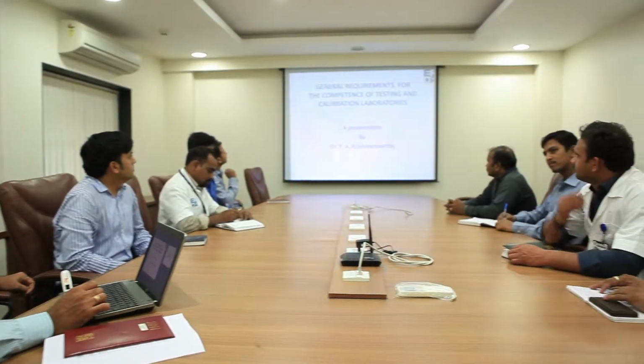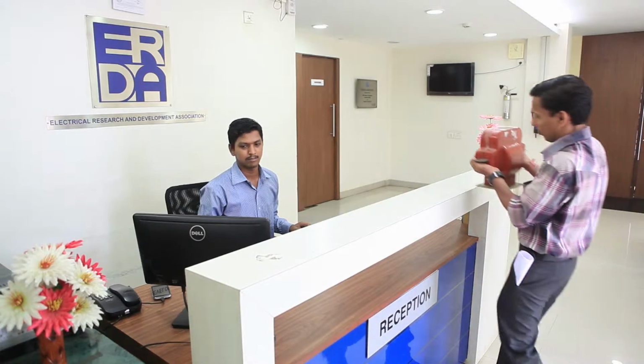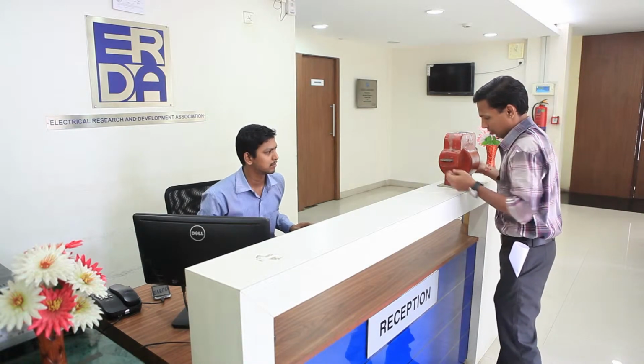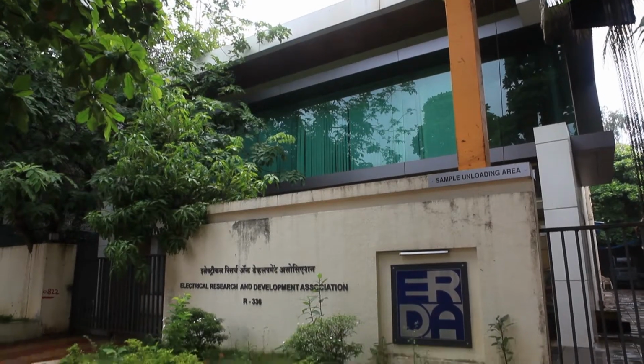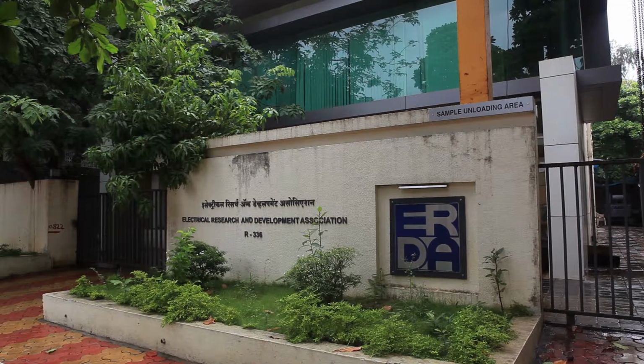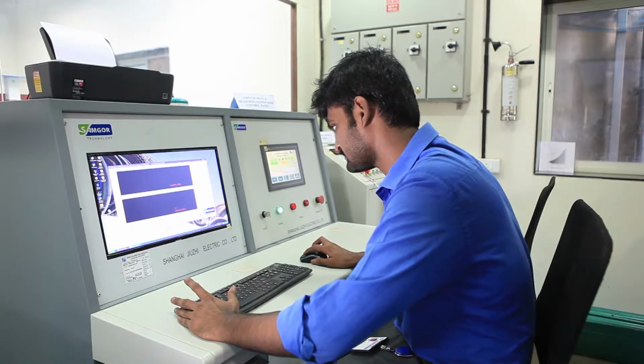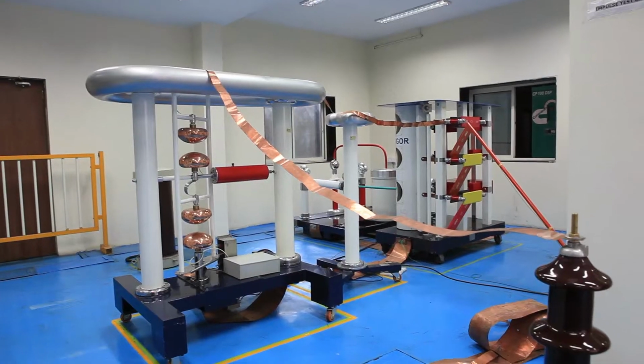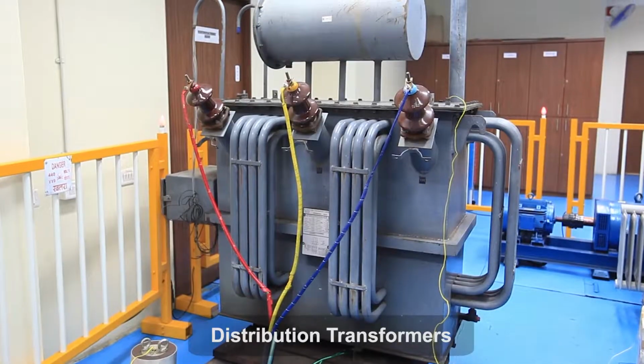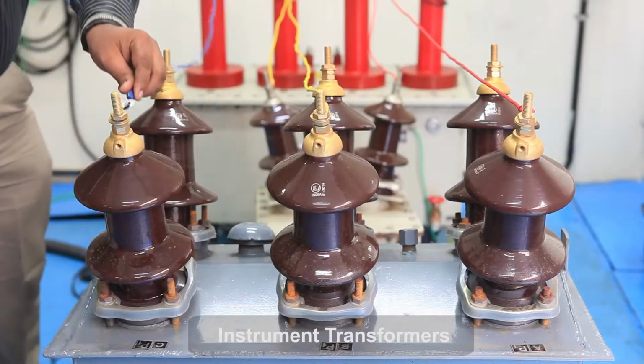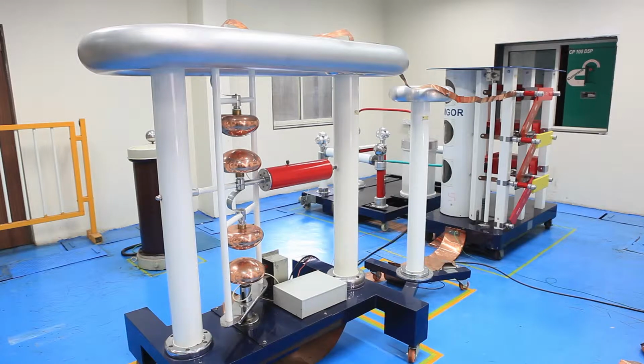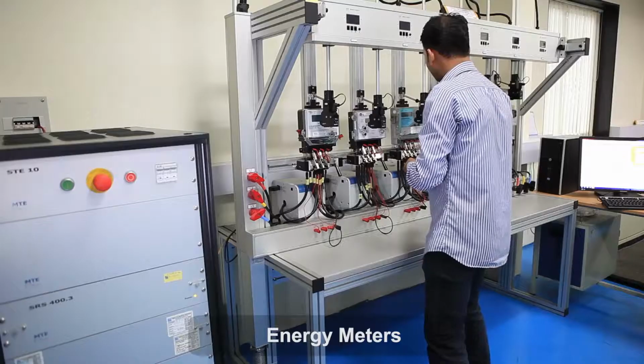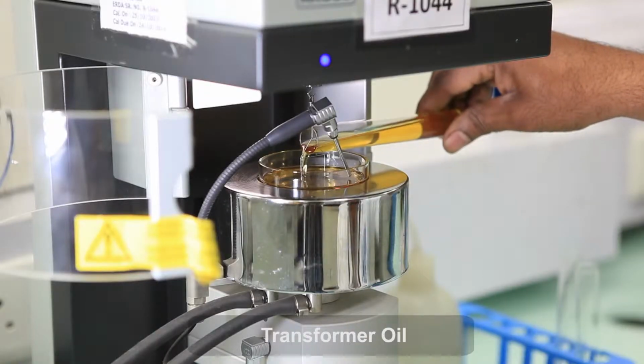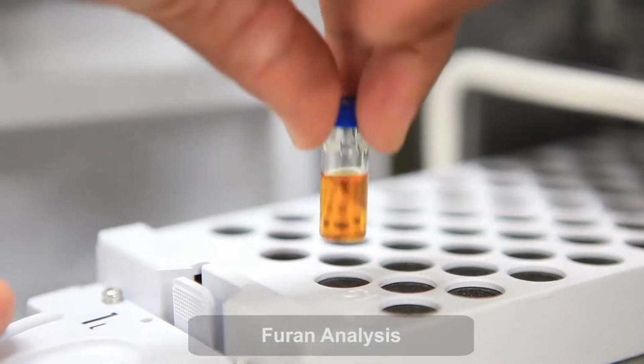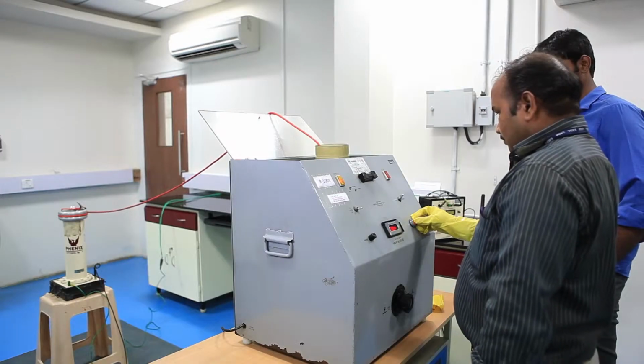In our endeavor to serve the growing list of customers in India and abroad, a new regional laboratory known as ERDA West has been established in Navi Mumbai, Maharashtra. ERDA West has test facilities for 33 kV class products like distribution transformers, instrument transformers, high voltage test, impulse test, energy meters, transformer oil, DGA, Furan analysis and electrotechnical calibration.